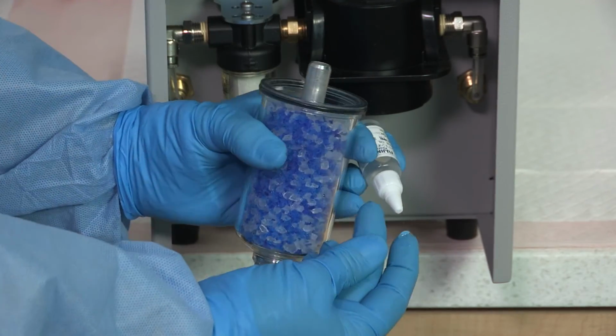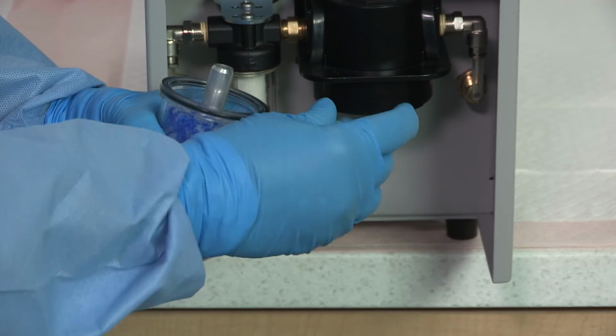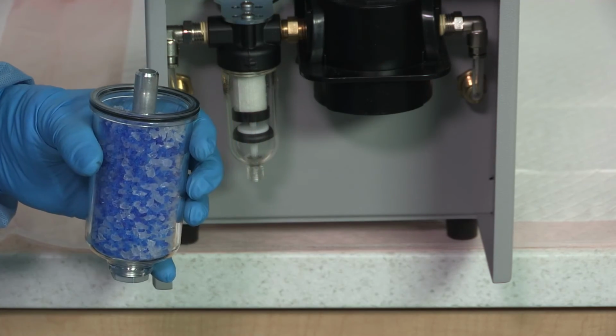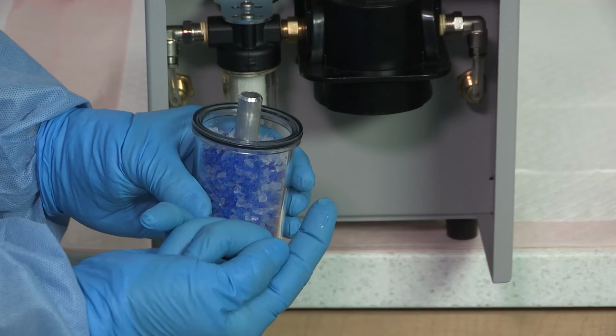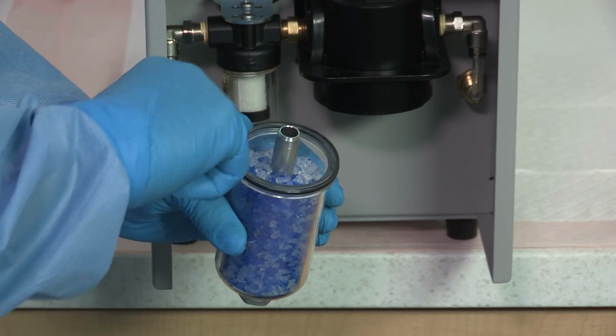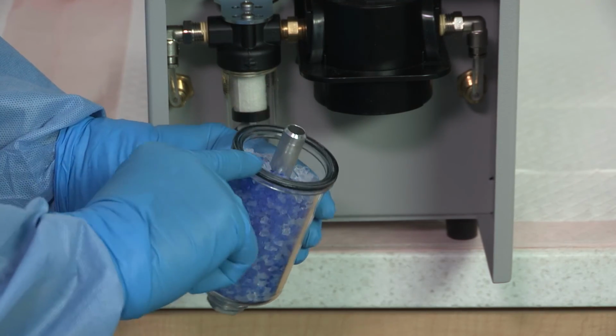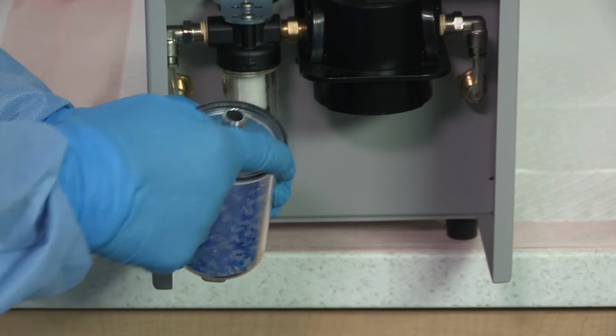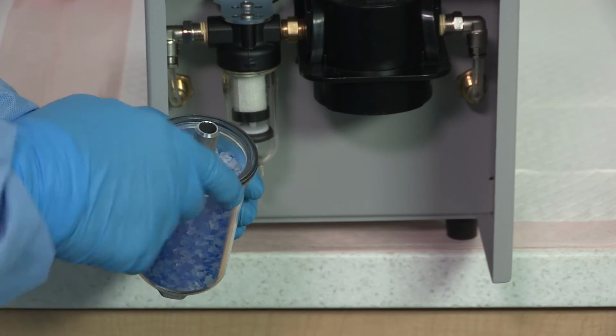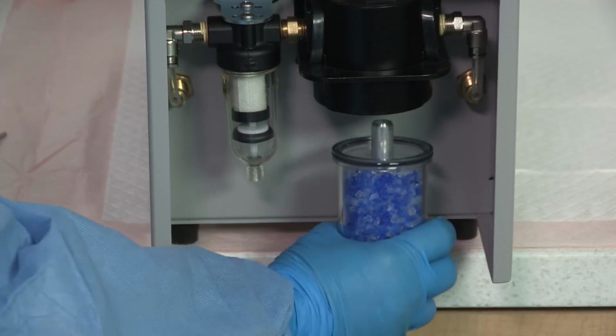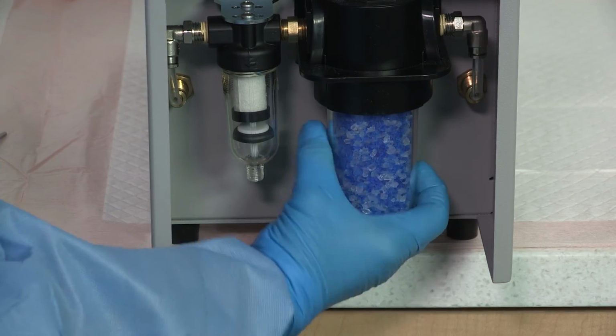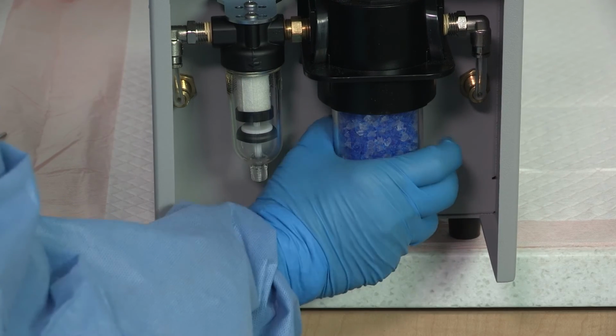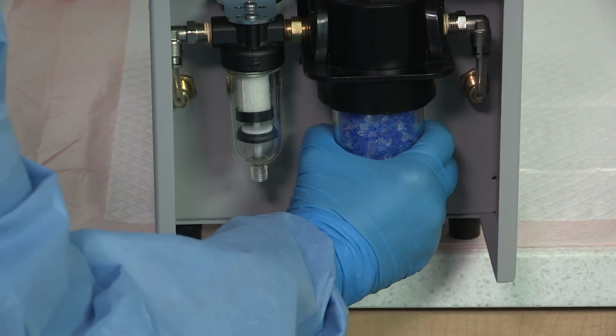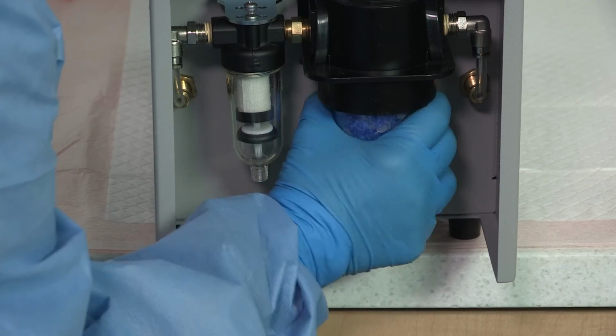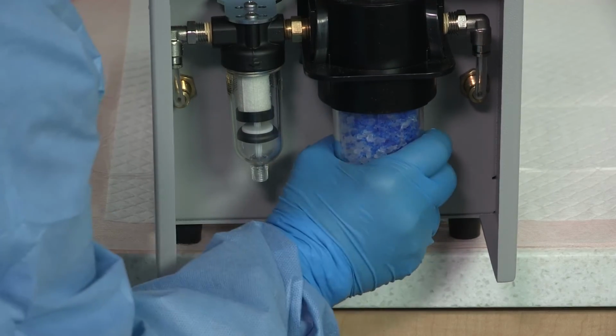After adding the crystals, lubricate the O-ring with a small amount of silicone oil applied with gloved fingers and ensure that there is no dust on the O-ring. If there is not a good seal or the crystal jar is not seated correctly, the daily QA test or subsequent leak tests will fail. Return the glass bulb to its original housing by placing one hand on top of the unit while inserting the bulb into the bulb housing structure. Apply careful upward pressure while twisting the bulb in either direction to help it pass through the tight gasket seal and for it to seat into the bulb housing structure.